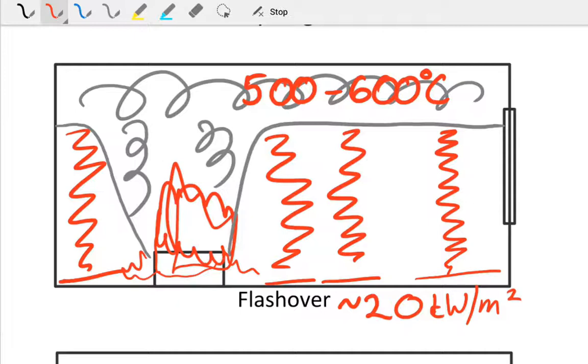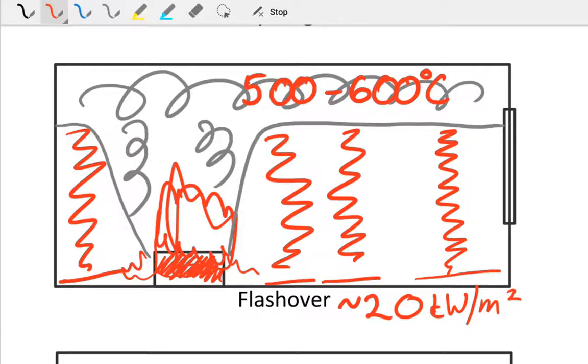When you get to a stage where the radiation is around 20 kilowatts per square meter—and this will depend on what's in the room, it might range up or down—pretty much everything will spontaneously ignite. Even though our package may be in one corner of the room, the radiation causes everything within the room to ignite no matter where it is.